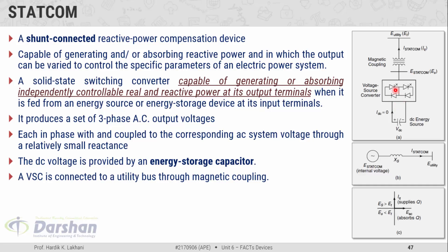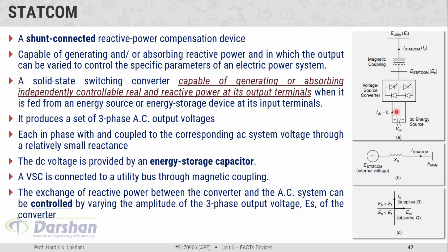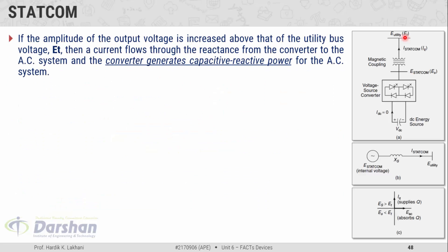The voltage source converter is connected to the utility bus through this magnetic coupling, which is the coupling transformer. The exchange of reactive power between the converter and the AC system can be controlled by varying the amplitude of the three-phase output voltage ES of the converter. This magnitude can be controlled by controlling the power semiconductor devices used in the construction of the voltage source converter. If the amplitude of the output voltage is increased above that of the utility bus voltage, then current flows through the reactance from the converter to the AC system, and the converter generates capacitive reactive power for the AC system.